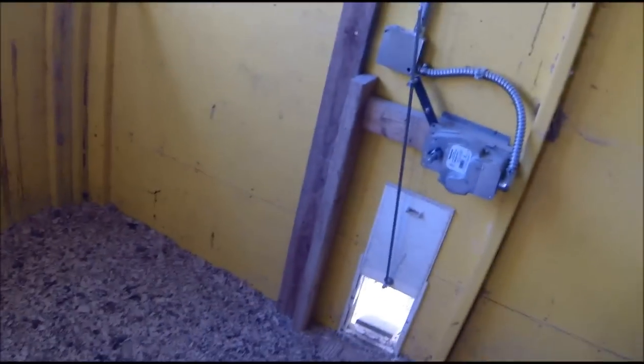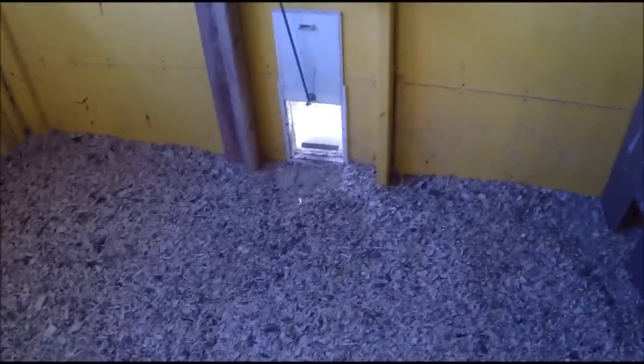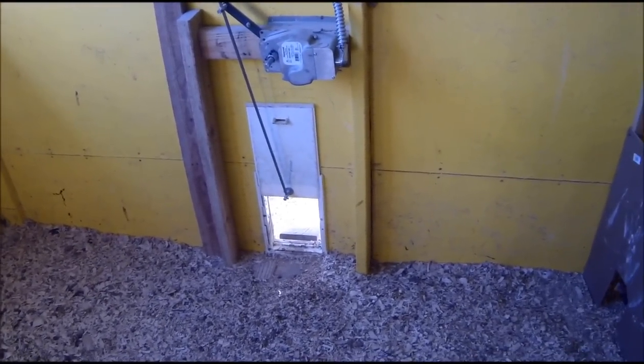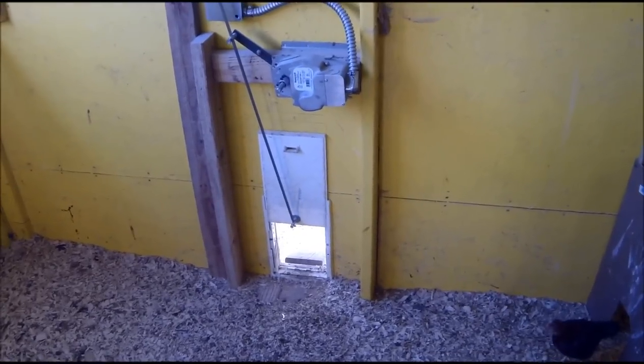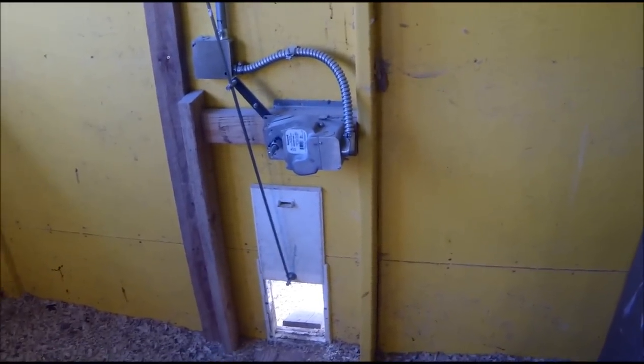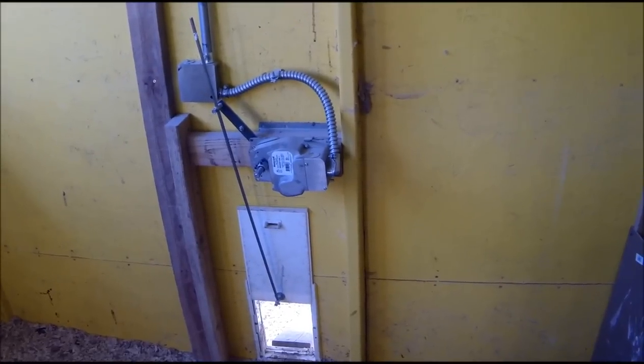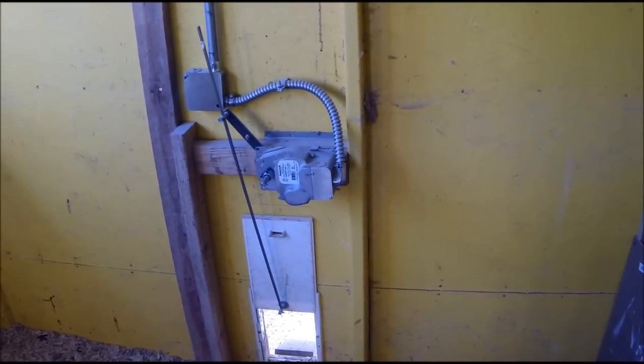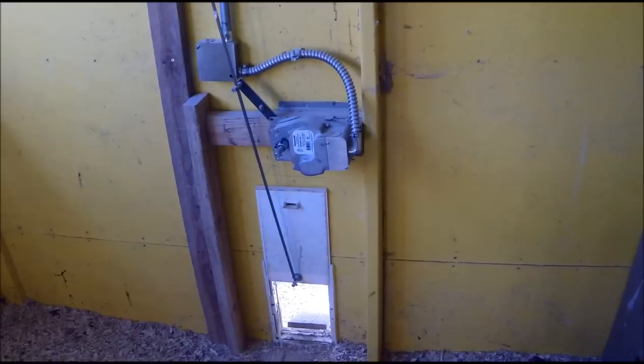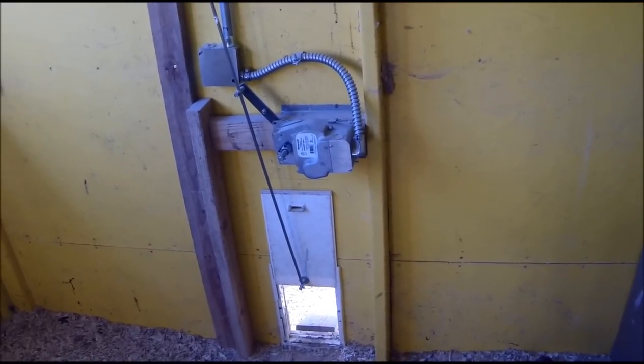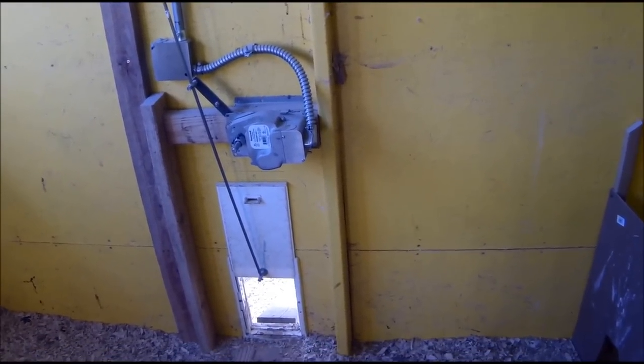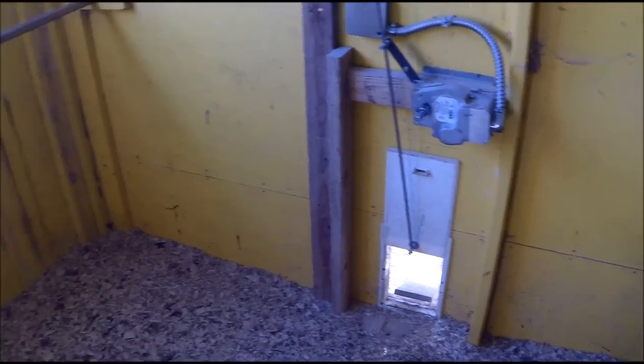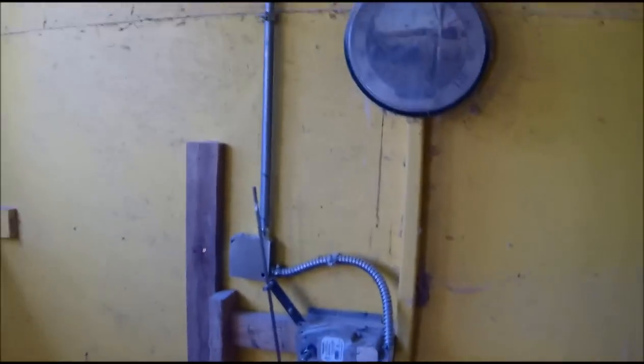Because obviously, if I kill power, like a photo cell would for your lights outside, it's going to close the door. So you could either use a relay, or you could set up your actuator to where when you energize it, it shuts the door. And the door would spring return up during the day when the photo cell would kill it.